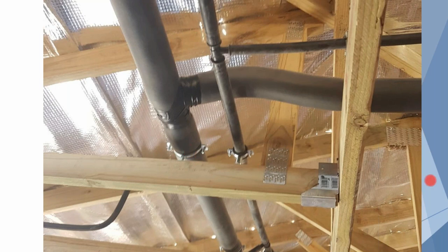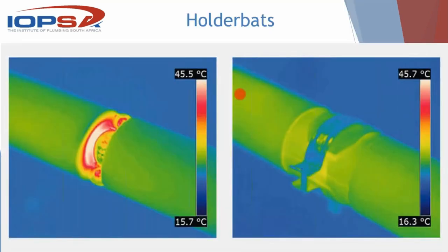That is far, far preferable to the alternative, where you stop the lagging, put in a pipe-sized holder bat, and then start the lagging again, and you can clearly see the heat loss through that little gap. So to answer the question, yes, you must have a holder bat that goes over the lagging, not the pipe. And whether it's metal or plastic, it doesn't matter. Whatever is going to be sufficient for the job. PVC holder bats, I find, work well. But those insulated metal brackets are better. Let's make no mistake about it.